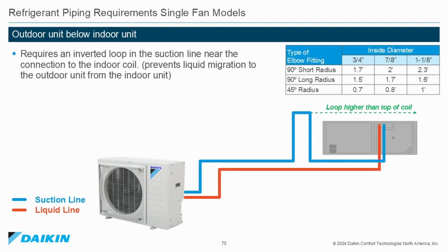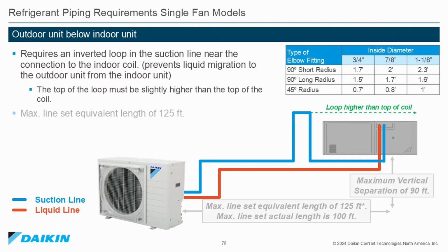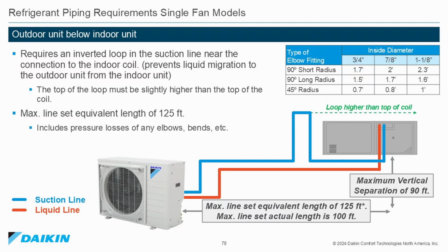When the outdoor unit is mounted lower than the indoor unit, the refrigerant lines require an inverted loop in the suction line near the connection to the indoor unit. This prevents liquid refrigerant migration to the outdoor unit from the indoor unit. The top of the loop must be higher than the top of the coil. Maximum line set equivalent length is 125 feet, which includes pressure losses from any elbows, bends, etc. Maximum actual length of the line set is 100 feet, with a maximum vertical separation of 90 feet.